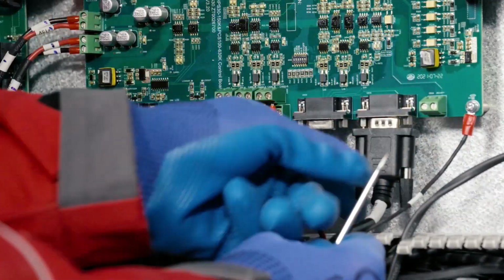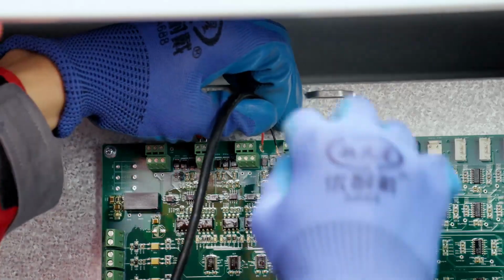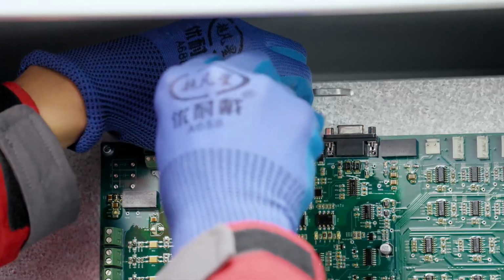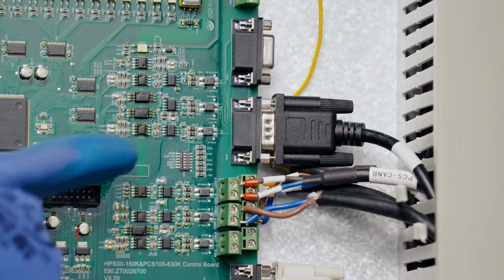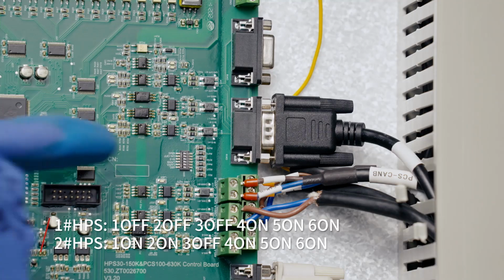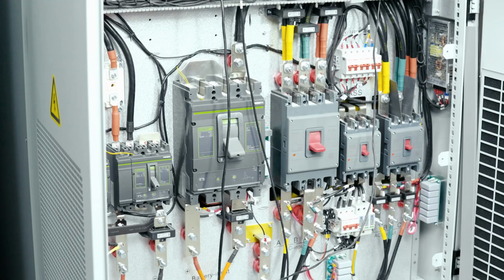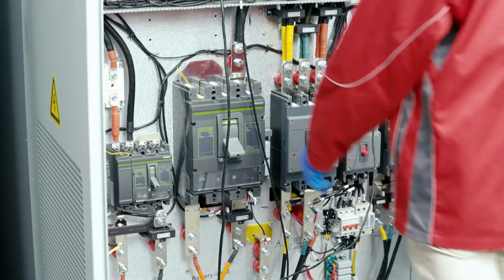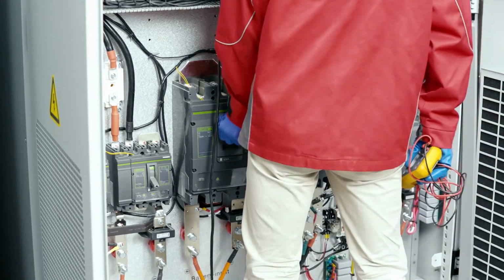Connect the parallel cable between HPS with DB9 communication cable. Connect CAN B of 2 ATESS. Distinguish H and L. Then do dip setting. Close the battery breakers of the 2 HPS and breaker of the battery system, and then power on the HPS screen.